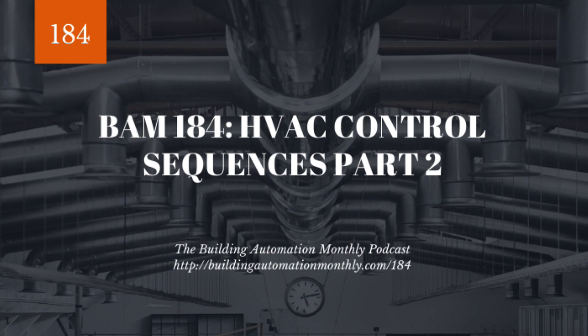It will drive the heating or cooling either through staged control in the case of most electric except for SCR, and most DX, it will drive it sequenced on. So it'll be, hey, stage one, stage two, stage three. In the case of gas, it will either turn it on, or if you modulate gas, it will go and modulate it. But typically gas is just on off as well. All right. And so you control temperature.